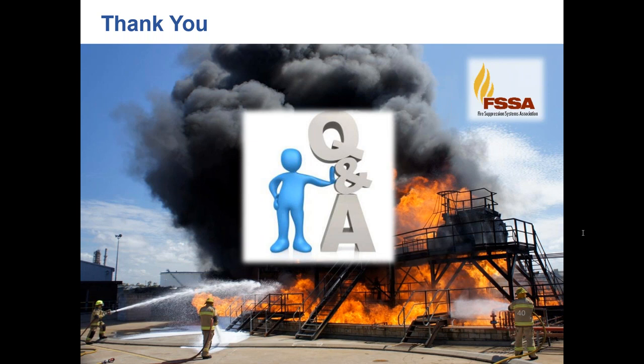Yeah, absolutely. That's one of the problems that are associated with the use of fluorine-free foams. We are kind of taking a step backwards. Over the years, because AFFF was so effective and had the film, we really didn't need super foam quality. So fire departments over the years have transitioned away from air aspirating foam nozzles and air aspirating foam tubes to standard water fog style nozzles. And they were very, very effective.